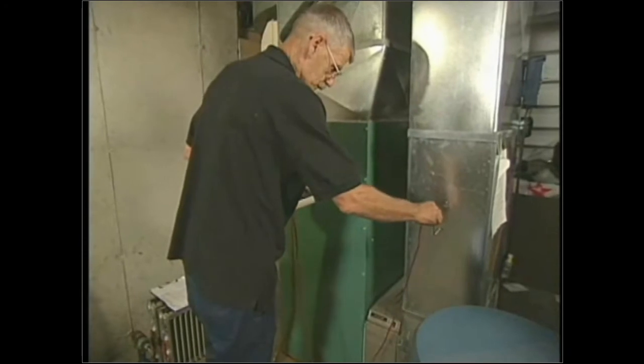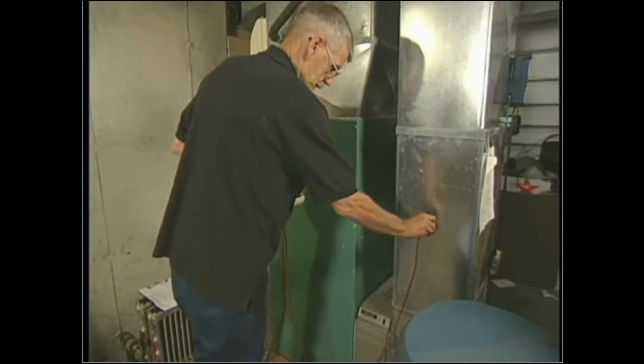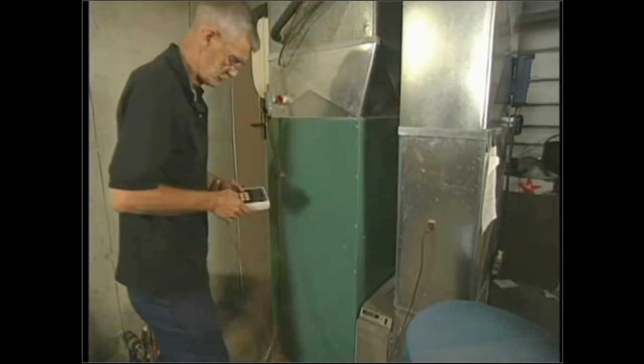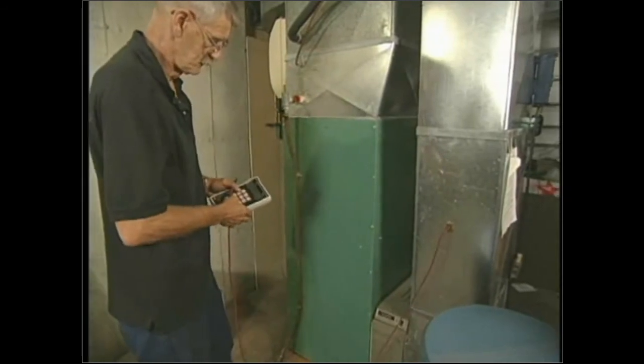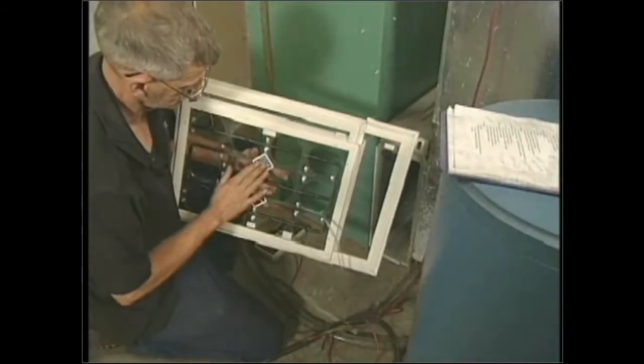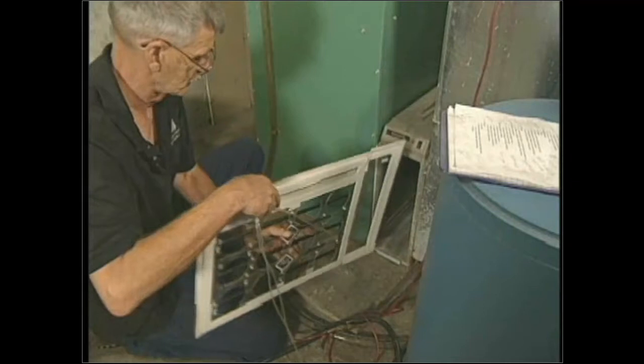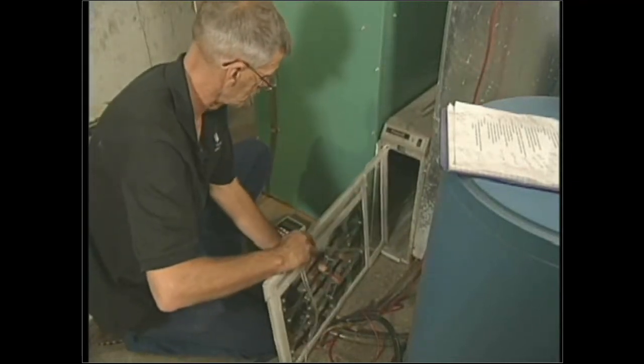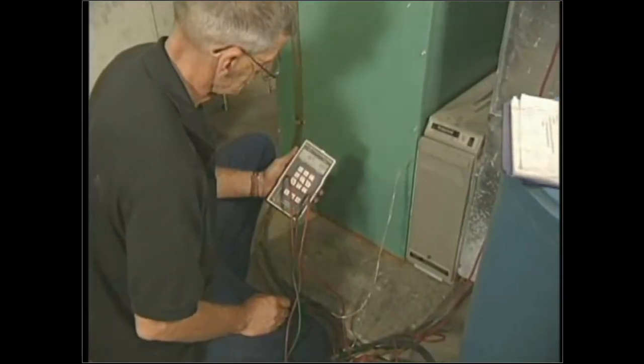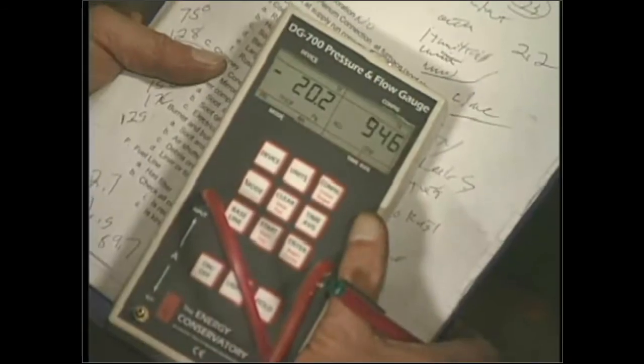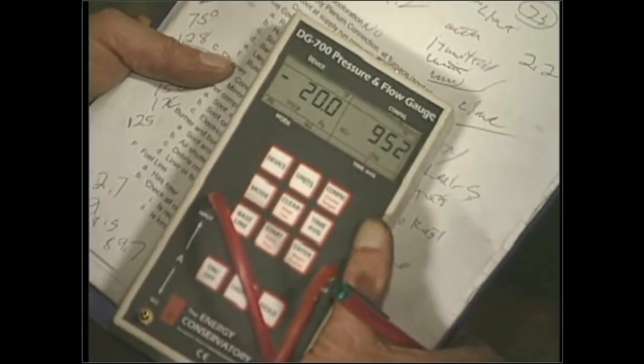And so really, from an auditor standpoint, when you're doing this test, you want to, first of all, test it with the homeowner's filter in place. A clean homeowner's filter in place. Then you take that out, you replace it with a flow plate, and then compare those two results. And this does it all for us. When we're all done, after we compared the two static pressure readings, one with this plate in and one with the original filter, it'll give us the CFM on this side.